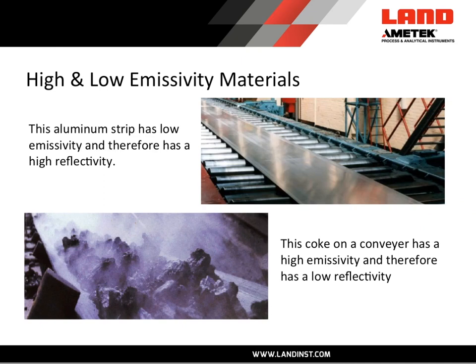In the upper photograph we see a strip of aluminum in a hot rolling mill, and our eyes show us that it is very reflective. Emissivity equals one minus reflectivity, so if something is very reflective it is not very emissive. Conversely, in the lower photograph we see coke on a conveyor belt — dark, rough, not very reflective — and therefore it has a high emissivity and a low reflectivity. Again, emissivity equals one minus reflectivity.